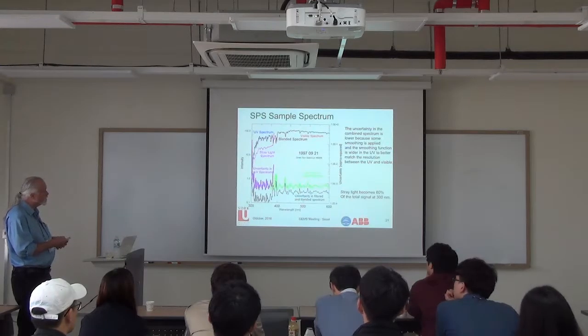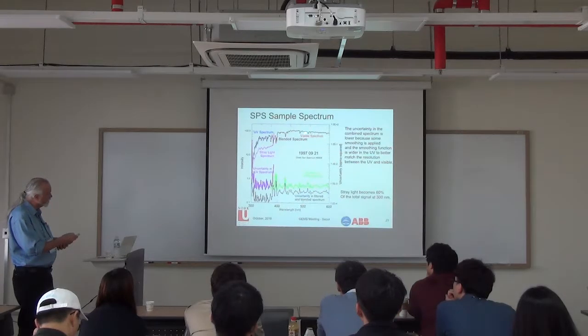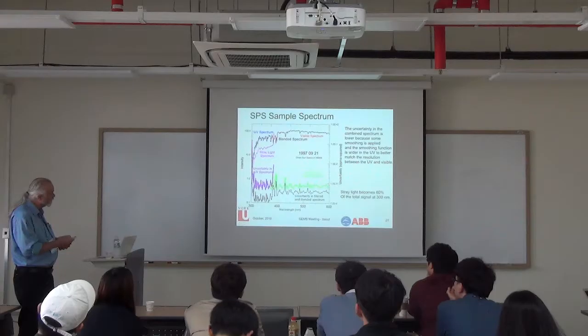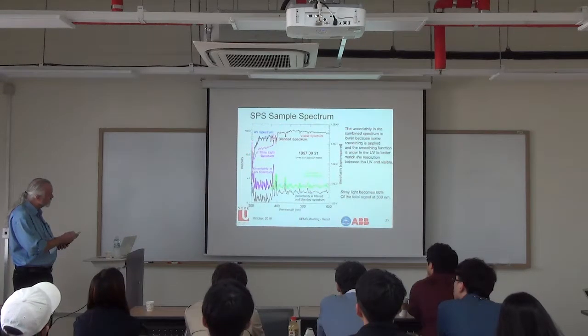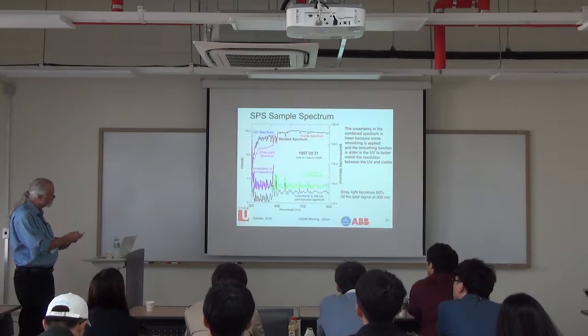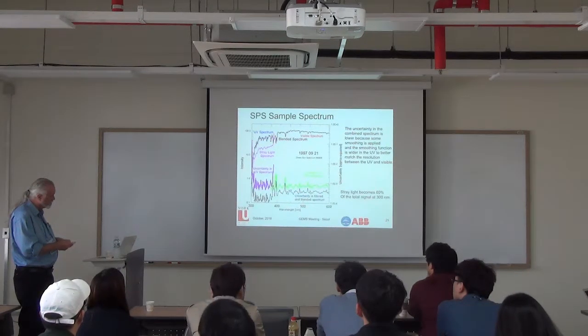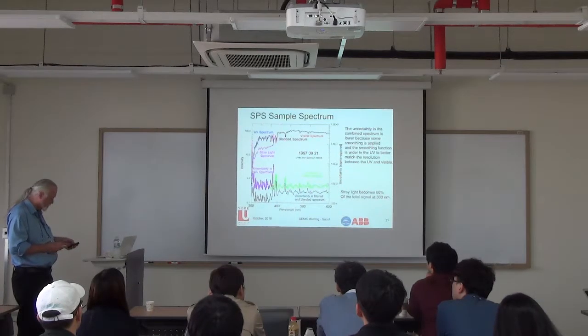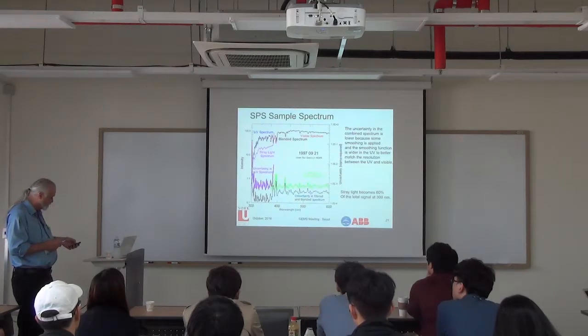You can also generate a noise estimate from the statistics on the spectrum. When blending the UV and visible spectra, a little filtering is applied to bring the UV resolution to match the visible, and then they're blended together. The noise level in the blended spectrum appears a little smaller due to improved statistics from the moving average.